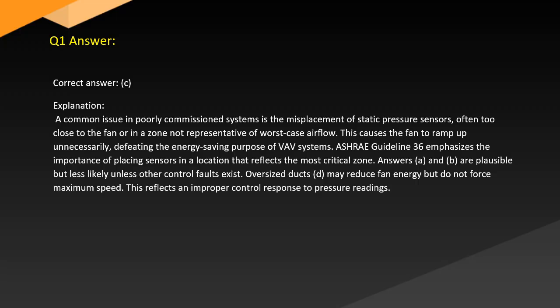A common issue in poorly commissioned systems is the misplacement of static pressure sensors, often too close to the fan or in a zone not representative of worst-case airflow. This causes the fan to ramp up unnecessarily, defeating the energy-saving purpose of VAV systems. ASHRAE Guideline 36 emphasizes the importance of placing sensors in a location that reflects the most critical zone. Answers A and B are plausible but less likely unless other control faults exist. Oversized ducts, D, may reduce fan energy but do not force maximum speed. This reflects an improper control response to pressure readings.